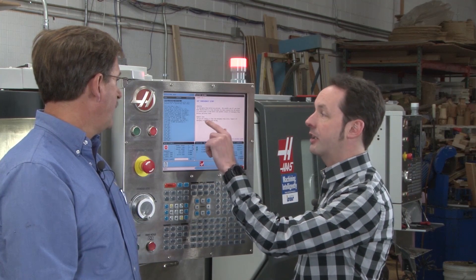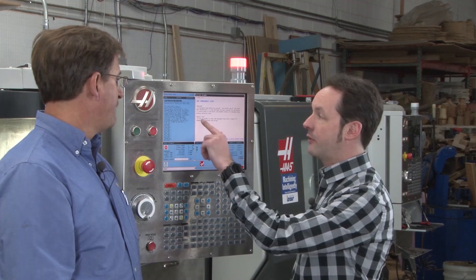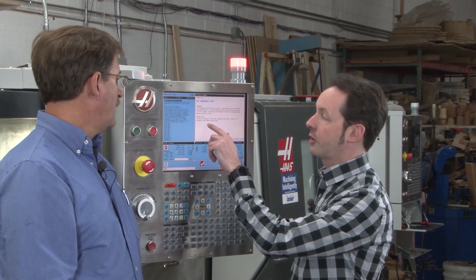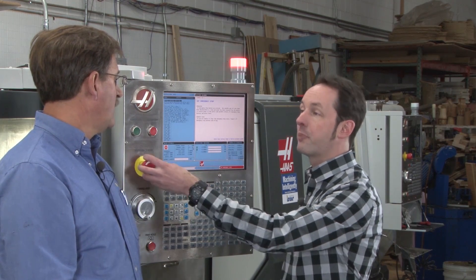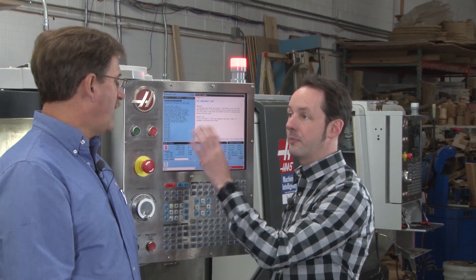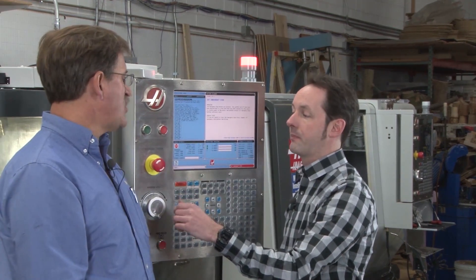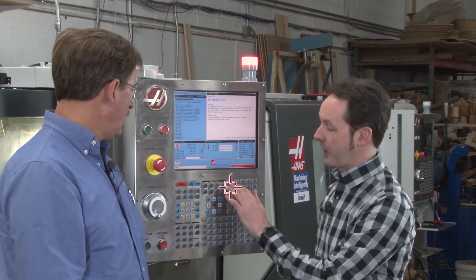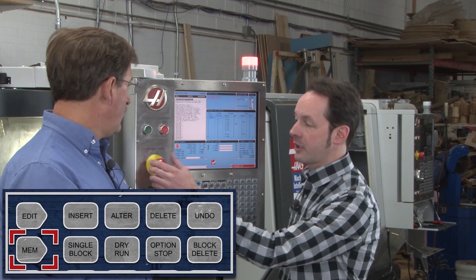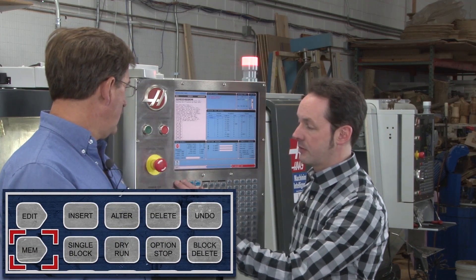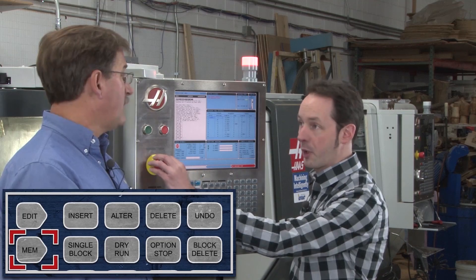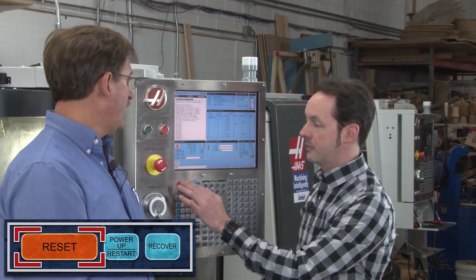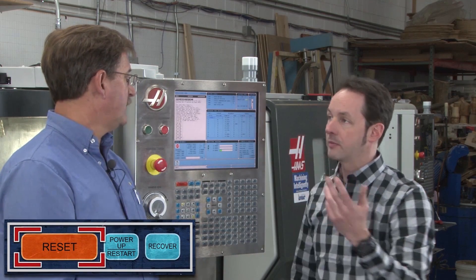And if you're the service tech, if you're unable to clear the emergency stop alarm, inspect all buttons — like if the button is screwed up, a pinched wire or something silly. You clear it, just fix the problem, and hit reset and you're good.